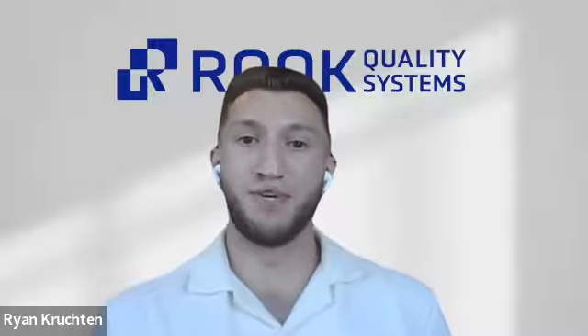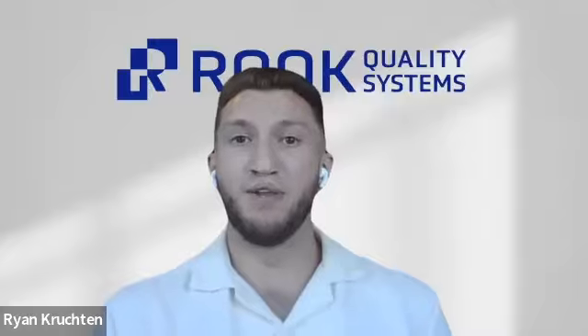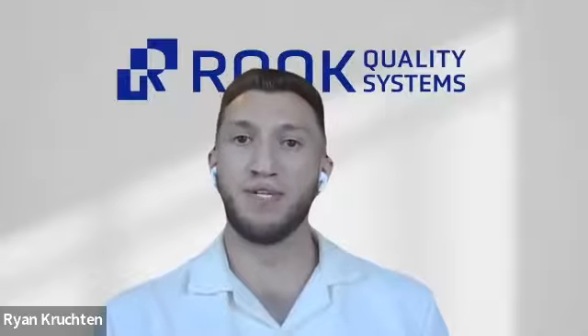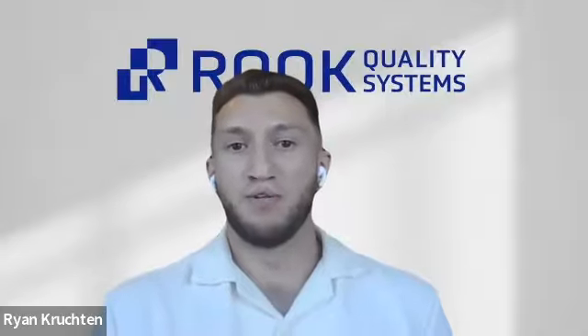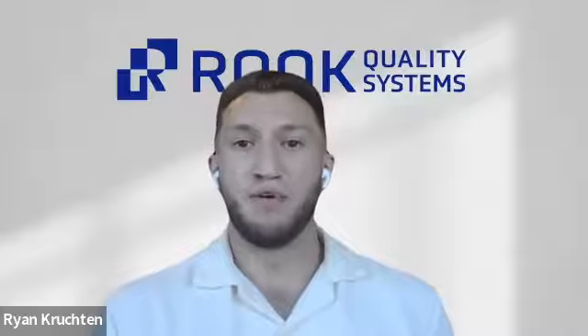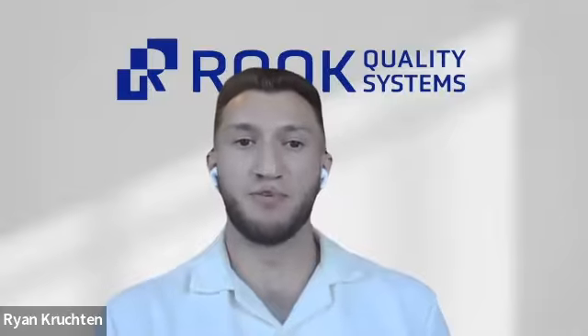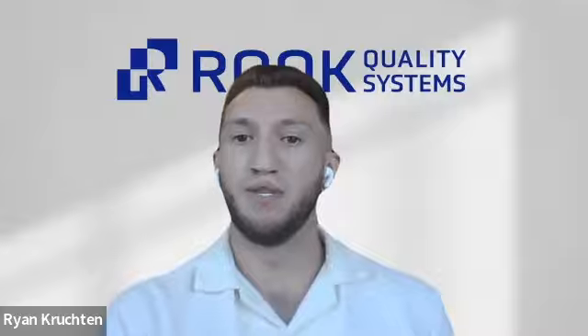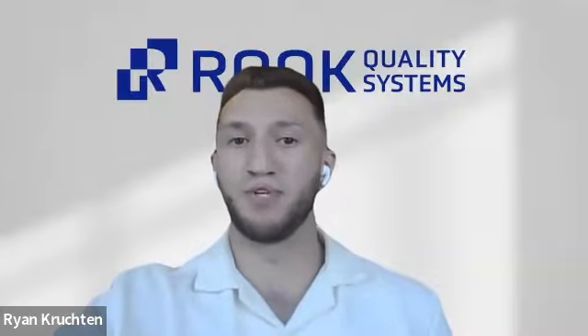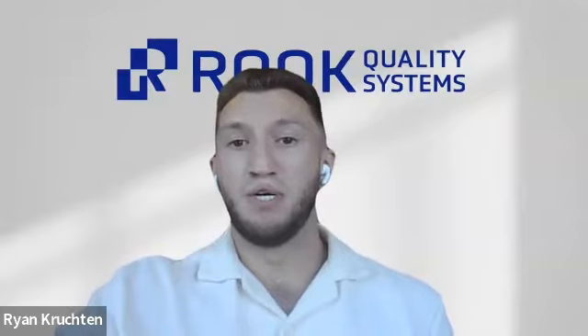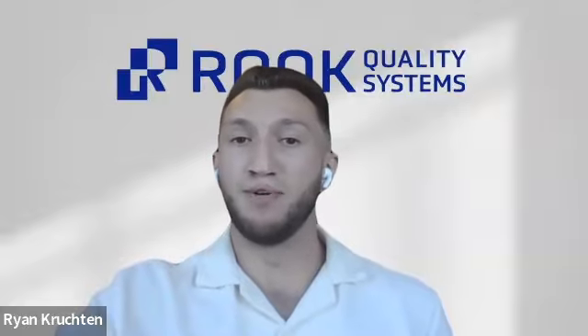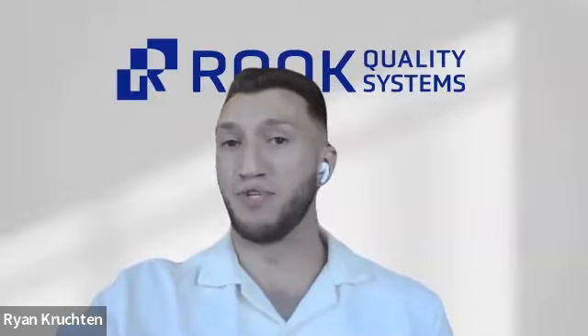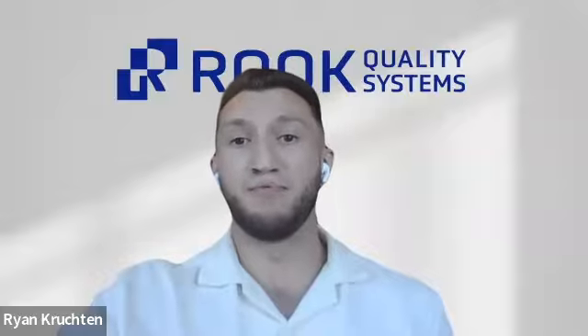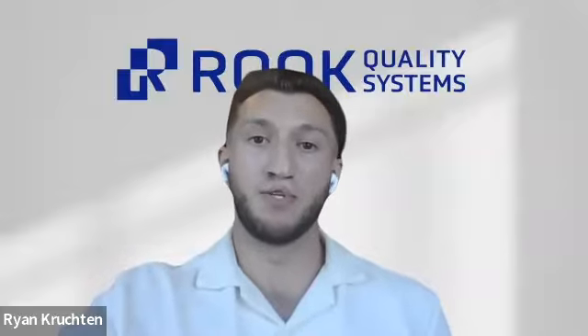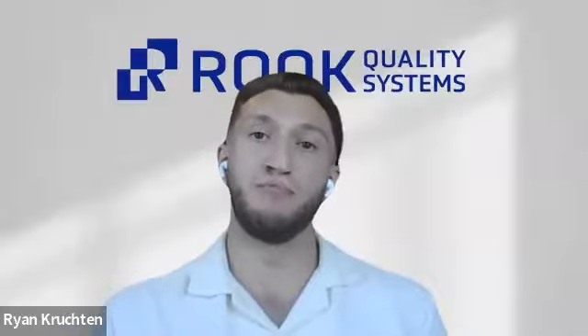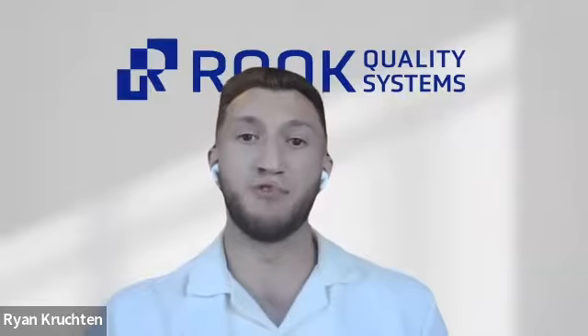Cybersecurity is a relatively new consideration for many development teams, and it will continue to evolve as the digital landscape around us changes. So like other aspects of device design, the FDA expects a risk-based approach starting at the planning phase. And this includes a cybersecurity plan along with your software development plan. In the design phase, it typically includes threat modeling, security controls, and initial risk management activities. And if you're performing an agile method, this could look like performing each of those deliverables in a much more abbreviated fashion per sprint.